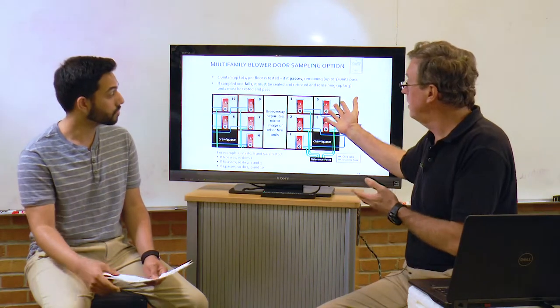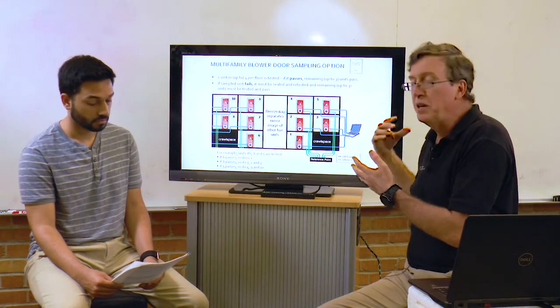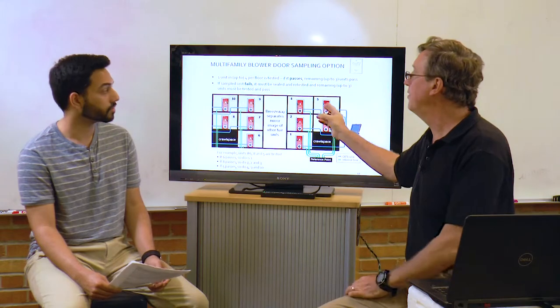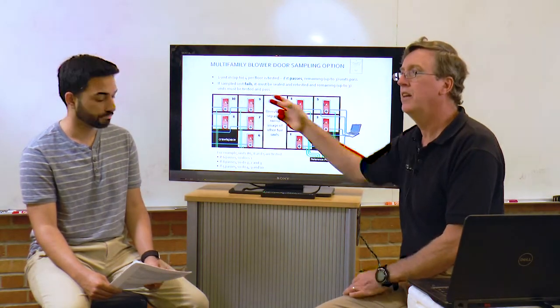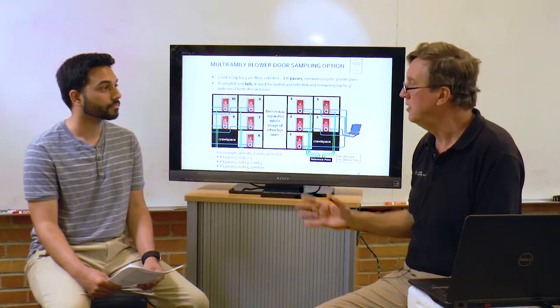If I blower door test unit 5 and it does not pass, I have to retest it. Basically, I have to seal it, fix it, retest it, and then I also have to test 4, 9, and 10. So there's some incentive for me to do a good job, so hopefully I can minimize the additional testing required.